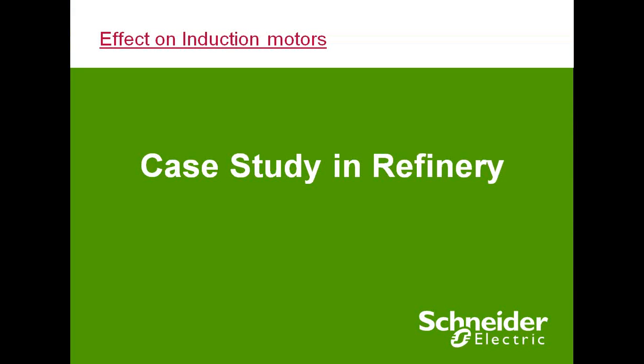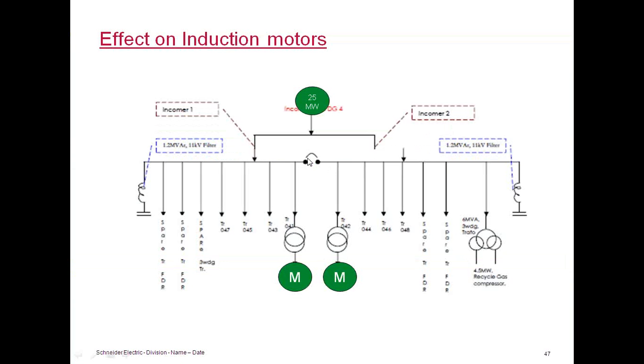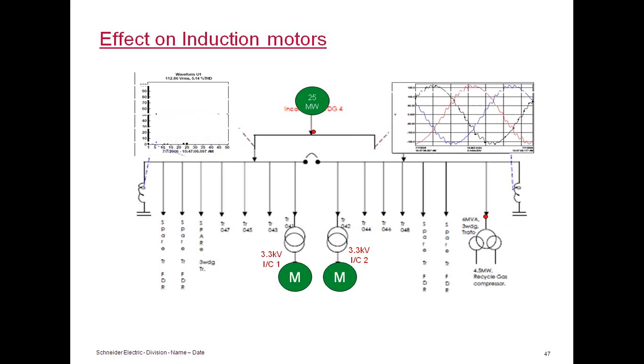So we have a case study in a refinery, this is the single line diagram. We have a 25 megawatt generator, and we have 11 kV buses on both sides with the bus coupler on condition. There is a 12-pulse drive, 4.5 megawatts, connected to the 11 kV supply through a 3-winding transformer. Harmonics from this drive are distributing to all the loads like this. This is a voltage waveform that we measured at the 11 kV bus. It's full of harmonics, and this voltage harmonic is driving current into the incomer to 3.3 kV, where we have a lot of induction motors. The customer had significant motor failures at 3.3 kV.